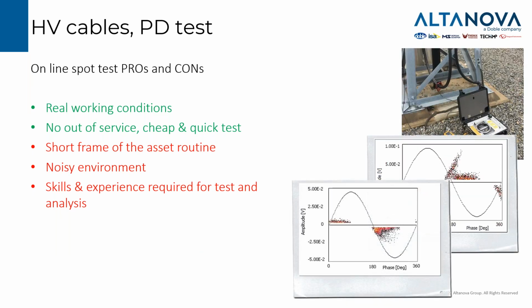Some positive and negative aspects of online spot testing. We are checking the system in the real working condition. We don't need any outage. We don't need any external power supply. So it's a cheap and quick test. But we just take a look at a snapshot of the asset routine. We can have a noisy environment. And for the data analysis, we may need some skills and experience because, for instance, if we are testing in an outdoor high voltage substation, we will have all the disturbances from the corona and the surfaces of the outdoor components. Those will enter the measuring chain, and we need to differentiate between what is external to the insulation and what is internal to the insulation. That is the dangerous and critical point.